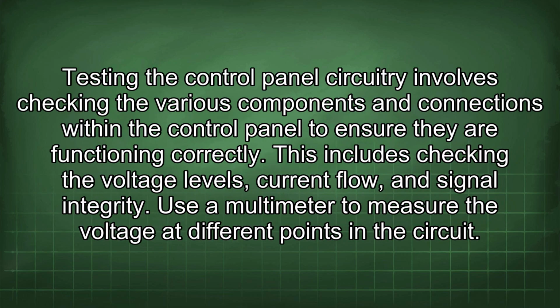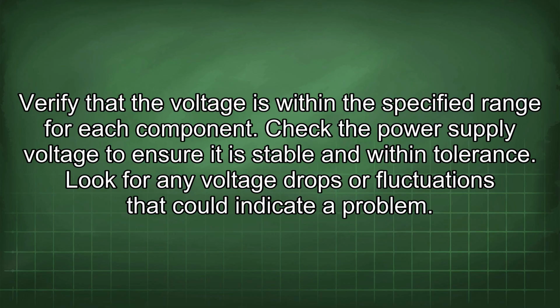Testing the control panel circuitry involves checking the various components and connections within the control panel to ensure they are functioning correctly. This includes checking the voltage levels, current flow, and signal integrity. Use a multimeter to measure the voltage at different points in the circuit. Verify that the voltage is within the specified range for each component. Check the power supply voltage to ensure it is stable and within tolerance. Look for any voltage drops or fluctuations that could indicate a problem.